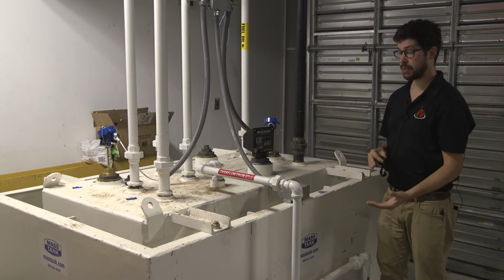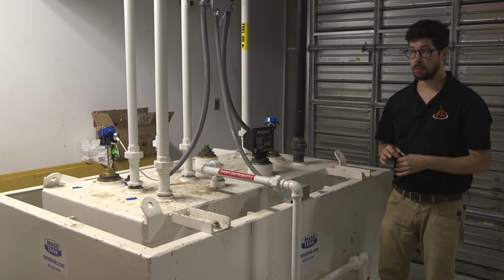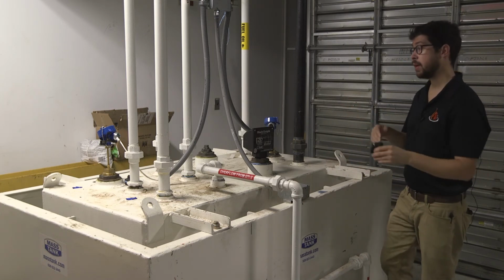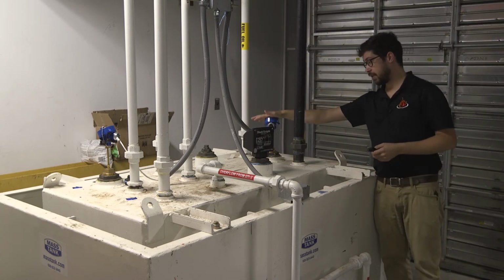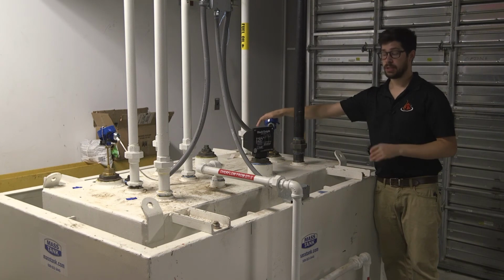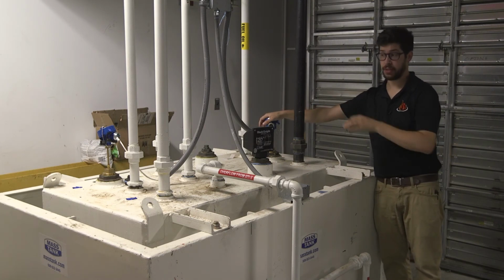We'll go out to the pumps. Maybe we have to switch the pumps over on the same system, or maybe we just simply say, hey, don't worry about it. We've got a whole different tank system out there. Let's just look at this float for now to buy us some time to troubleshoot that other system.